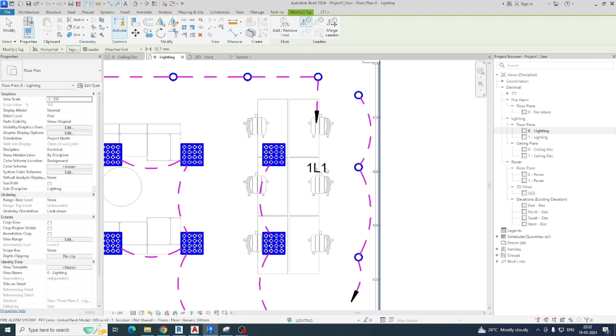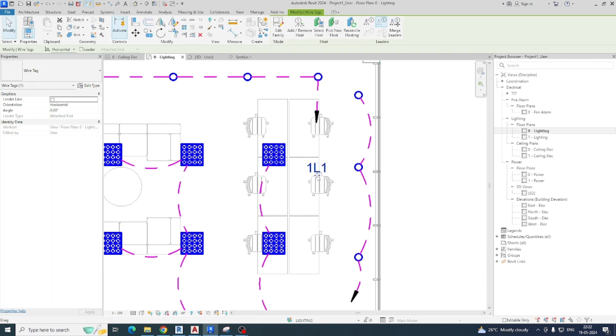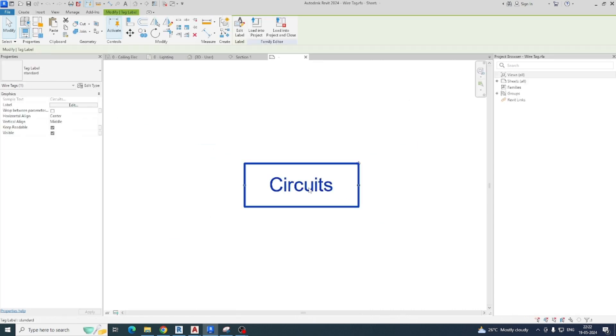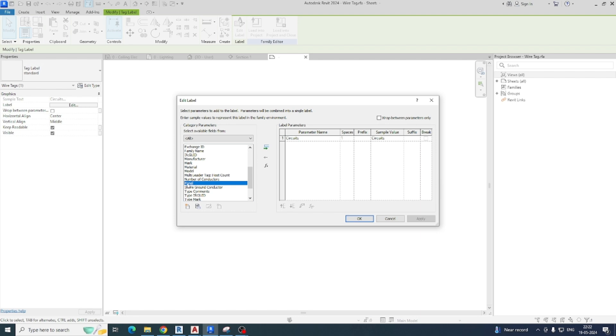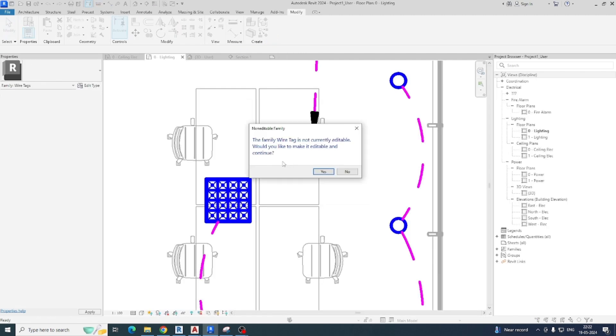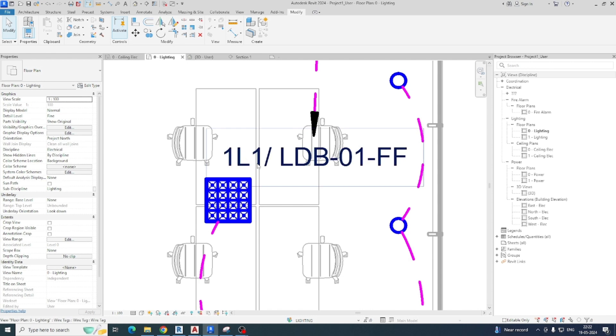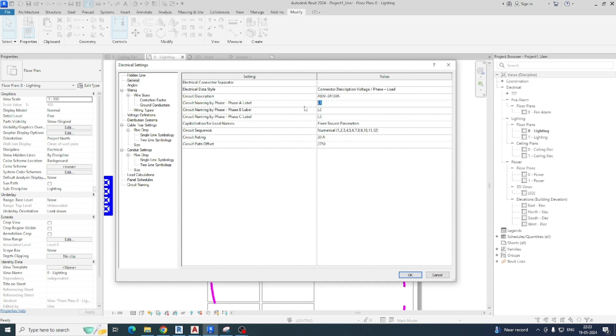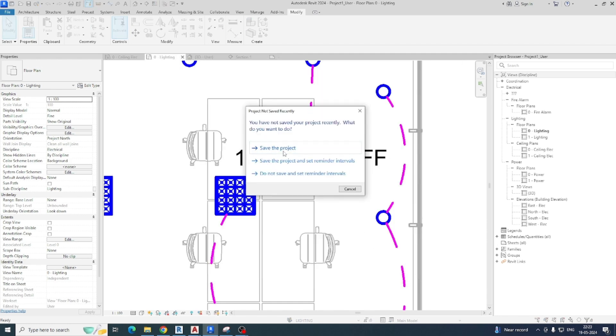It is showing L1 — just select this one, uncheck the leader. Why is it showing L1? We need to edit the family — it is showing circuits only. Add the panel family here, give a slash or dash, click OK, stretch it, load into the project and override. We need R1, L1 — so type ES for Electrical Settings, go to General panel, and here change to capital R, Y, and B phases. It will come up automatically as R1.